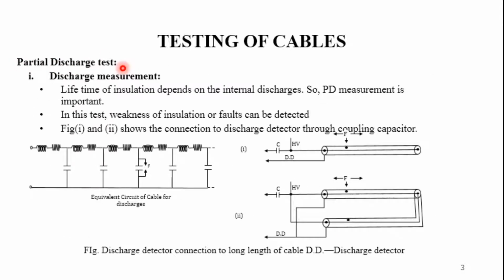Then the partial discharge test. There are different types of partial discharge measurement: discharge measurement, location, the scanning method and the life test. Coming to the first one, this is discharge measurement. Partial discharge measurement and discharge location are very important for the cable, since the life of the insulation at a given voltage stress depends upon the internal discharges. Also, the weakness of the insulation can be detected with the help of this type of test. The portion of the cable, if weak, may be removed if necessary. Then we can increase the lifespan of the cable.